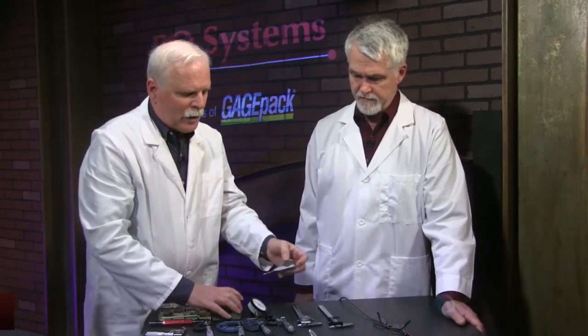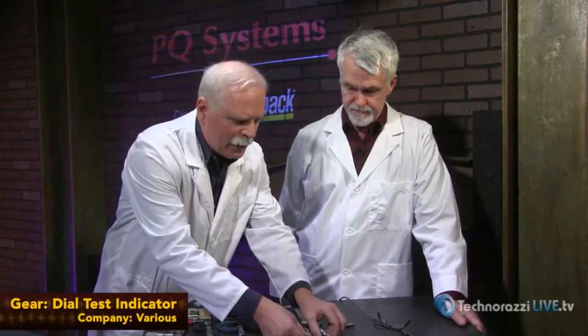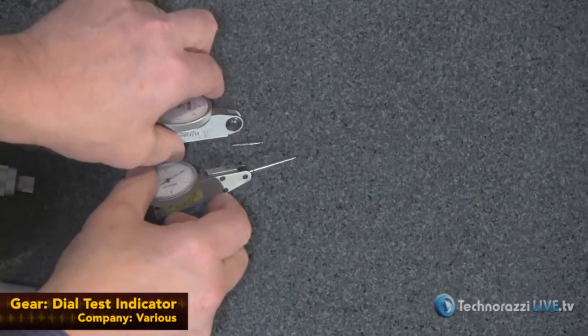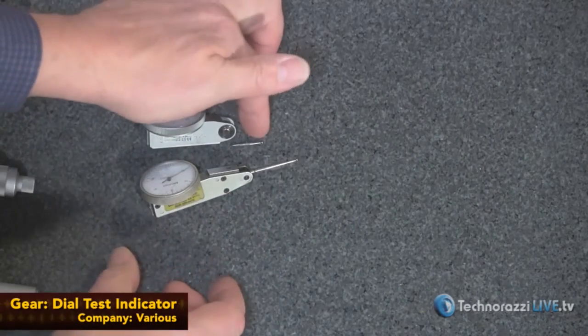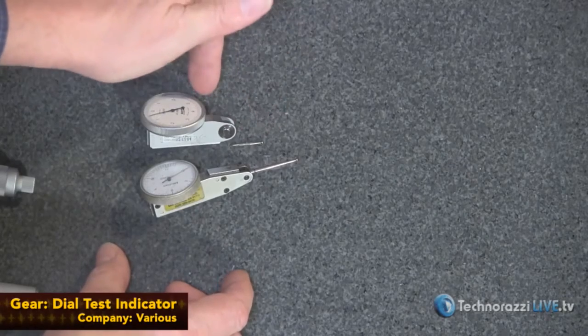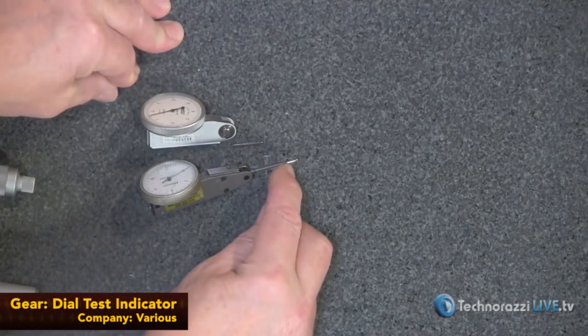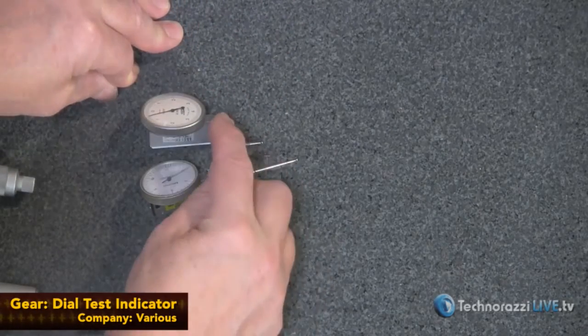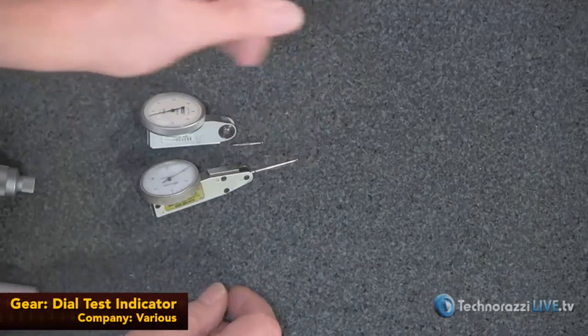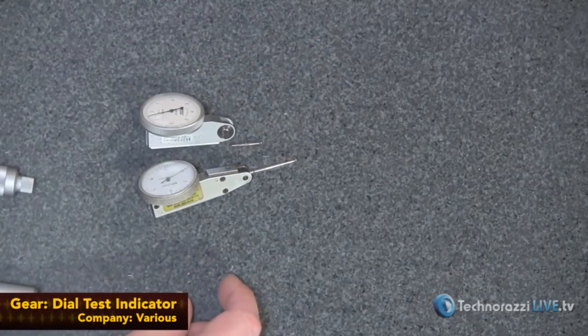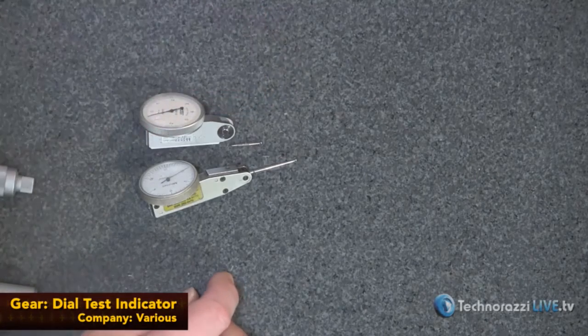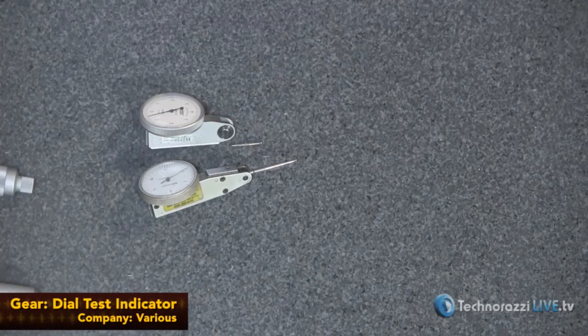Okay. Now here's a different indicator, and you'll notice the length of the contact point is quite a bit different. Contact points are specific to the indicator. Even if it fit on there, you could not put this long contact point on this one or the short one on here and get an accurate measurement. It doesn't vary. Once it's made for one, that's the only length that'll work.